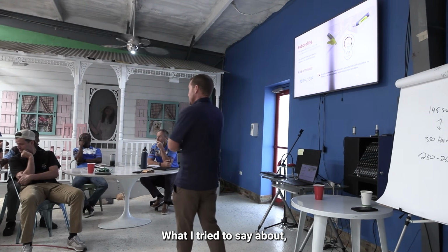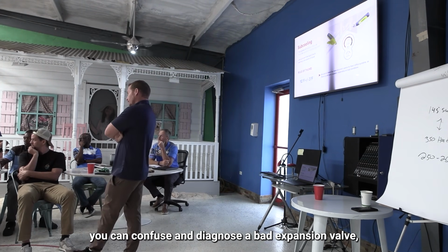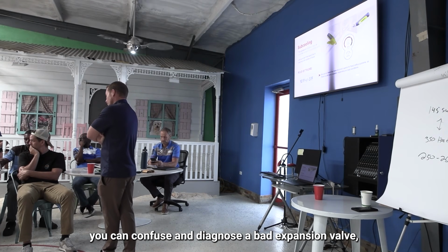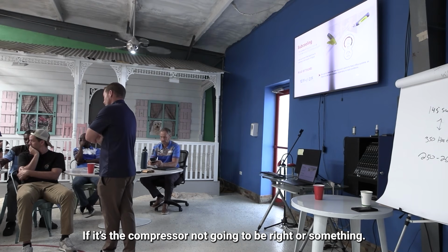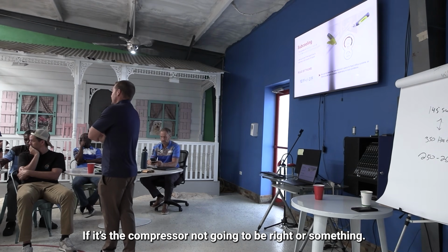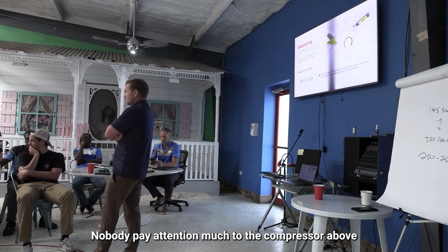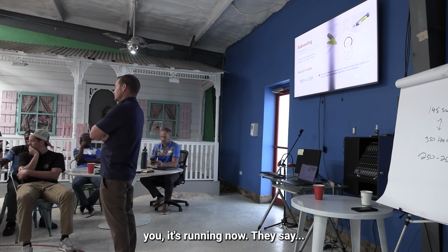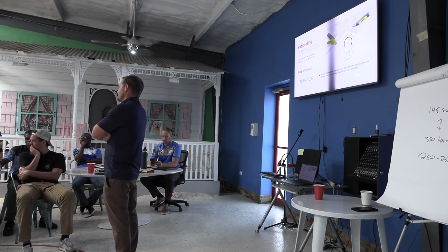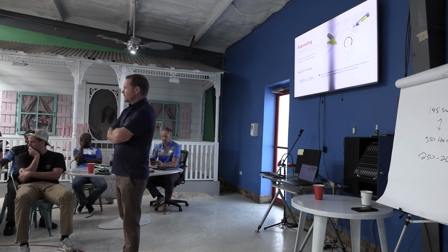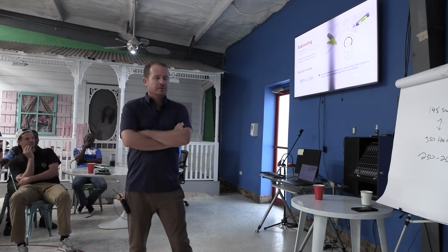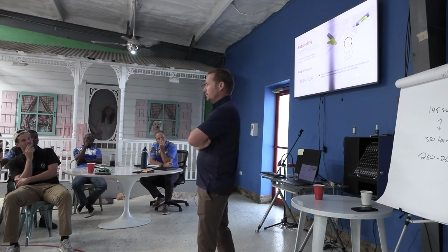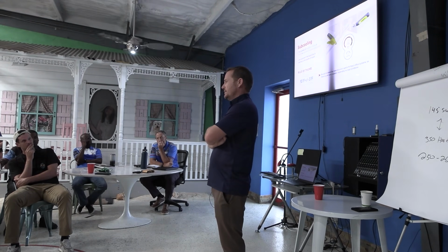Go ahead. This is what I'm trying to say, technicians get confused when diagnosing by the expansion valve, if it's the compressor not pumping right or something. Yeah. Nobody pays attention to the compressor not pumping because it's running. They say, well, it's running. Right, exactly. They're like, it's running, so yeah. And that's actually, and if we can get to it, I want to do a whole section on compressor troubleshooting because it's one of the more misunderstood things.